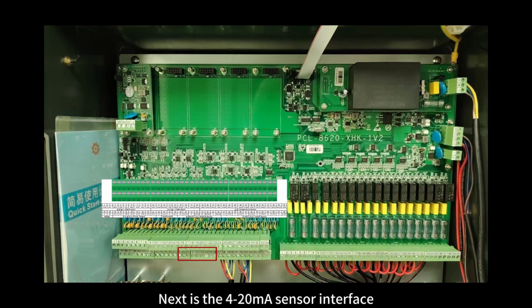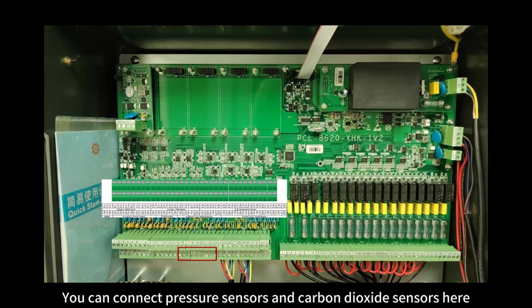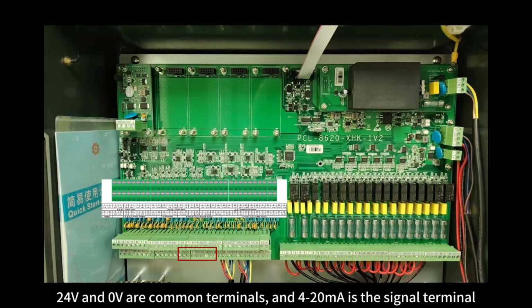Next is the 4 to 20 mA sensor interface. There are a total of 4 groups. You can connect pressure sensors and carbon dioxide sensors. Here, 24 volts and 0 volts are common terminals, and 4 to 20 mA is the signal terminal.